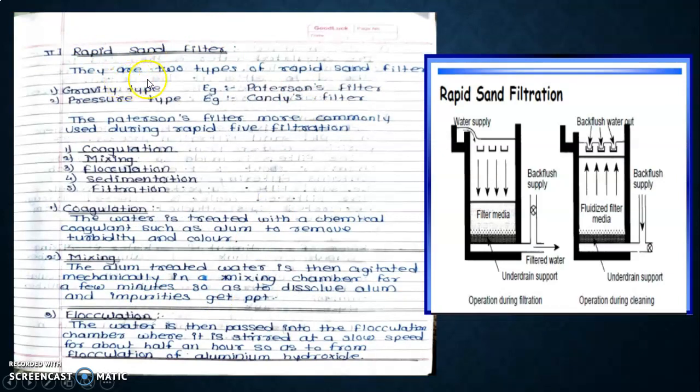Rapid sand filtration has two types: gravity type and pressure type. Paterson's filters are more commonly used during rapid sand filtration. The process includes coagulation, mixing, flocculation, sedimentation, and filtration. Coagulation means the water is treated with a chemical coagulant such as alum to remove turbidity and color. In mixing, the alum-treated water is then agitated mechanically in a mixing chamber for a few minutes so that the dissolved alum and impurities get precipitated.